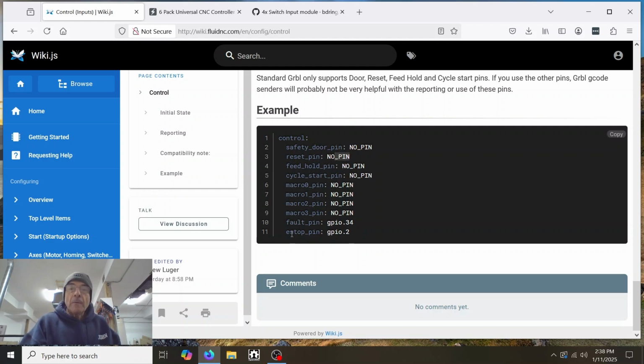So for instance, most of us implement an e-stop. I chose to put the e-stop on the safety door pin instead, because this way I can restart the machine after an e-stop press. If you put it on the actual e-stop pin, your job's done - you cannot restart the job, you're going to have to start over, and that isn't always easy.